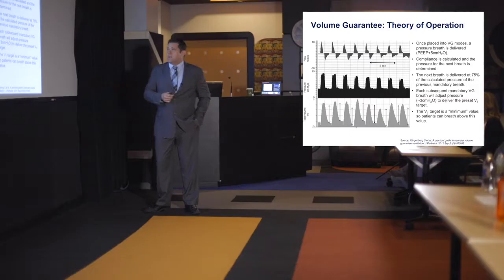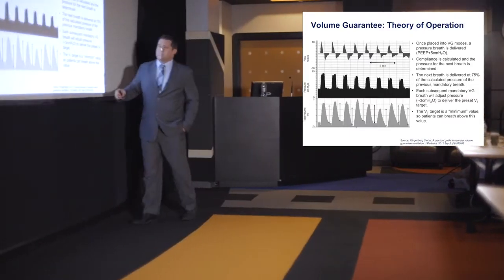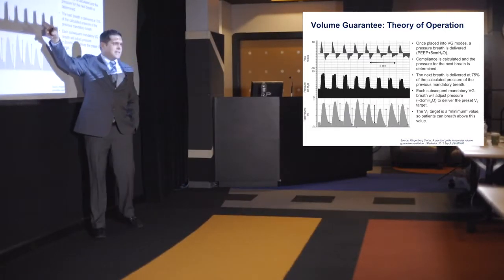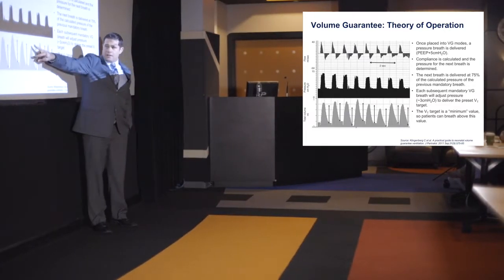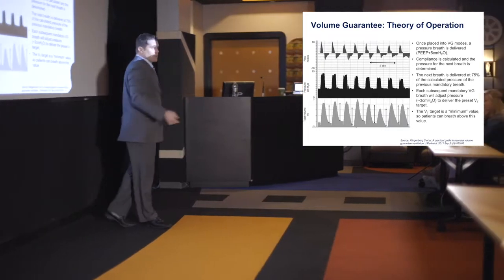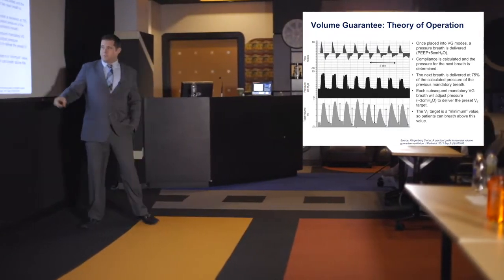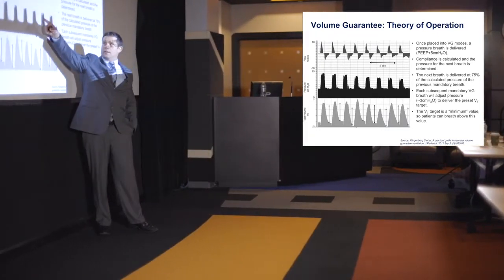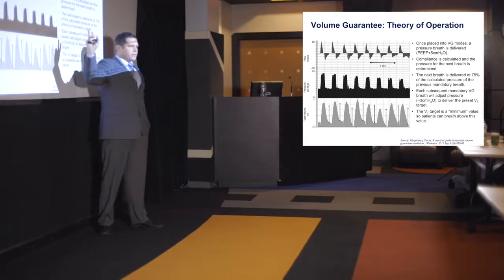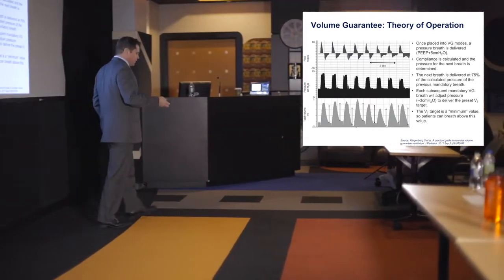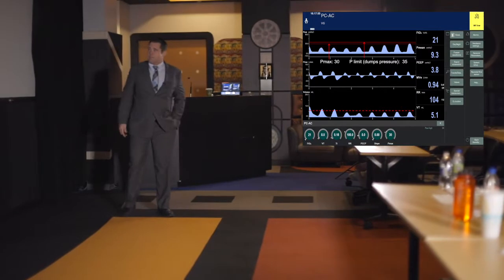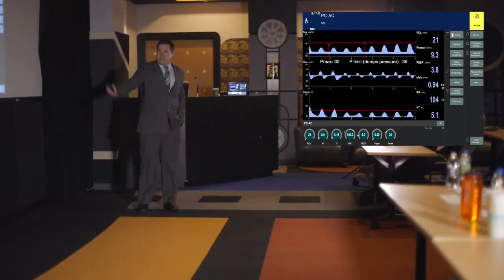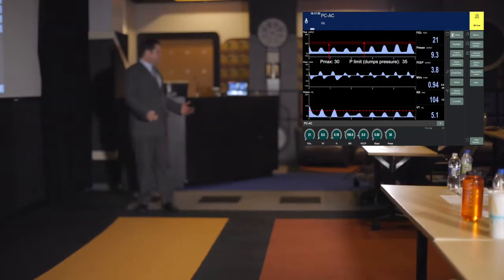So the way that it really works is breath by breath, the ventilator will wean the inspiratory pressure based on a tidal volume that's either being measured at the flow sensor or back at the ventilator. So if that tidal volume becomes excessive, which it is here, then it starts to drop the pressure by 1 or 3 centimeters of water pressure. Each ventilator is a little bit different. And I don't really try to focus on one ventilator in particular, but I just happen to have about 60 of these ventilators in my unit, so I have a lot of graphics.